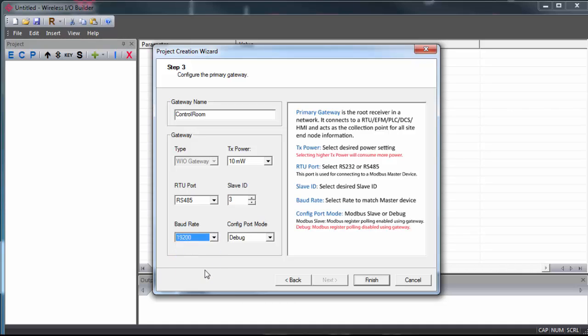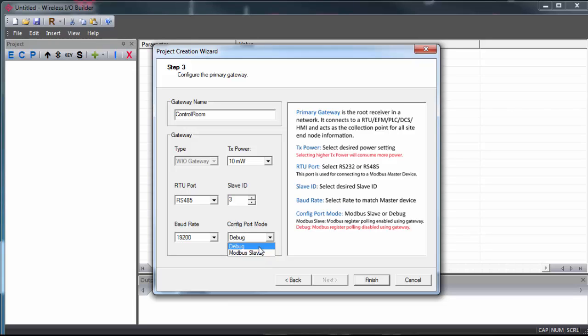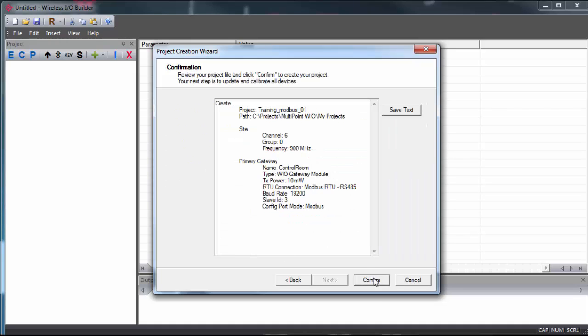And for config port, by setting it to Modbus slave, we'll be able to use our PC as a master to read and write registers to the gateway. By setting it to debug, you can see all the data coming out and any responses that you receive. But we can come back and adjust these settings later if we need to. So for now, click finish and confirm.